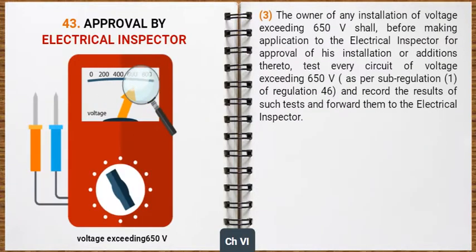The owner of any installation of voltage exceeding 650 volt shall, before making application to the electrical inspector for approval of his installation or additions thereto, test every circuit of voltage exceeding 650 volt as per sub-regulation 1 of Regulation 46 and record the results of such tests and forward them to the electrical inspector.